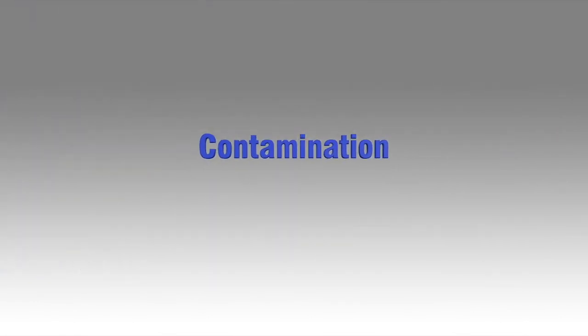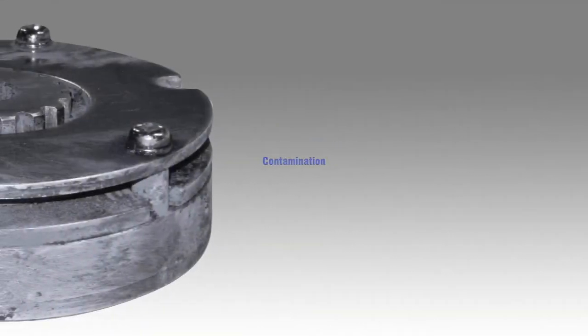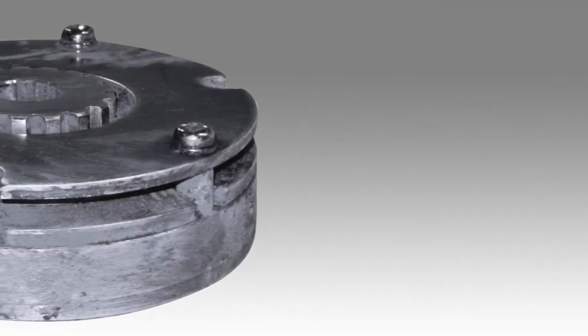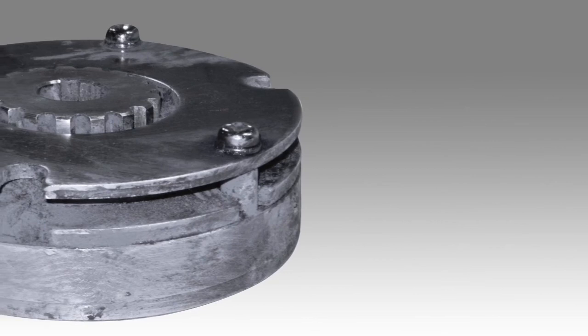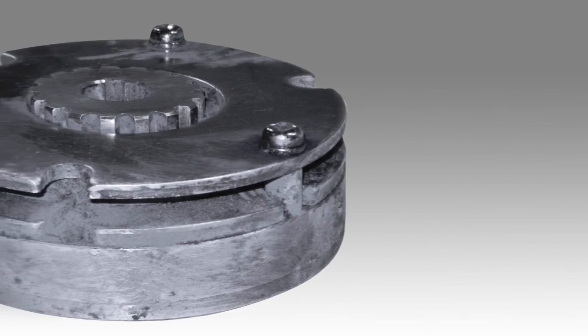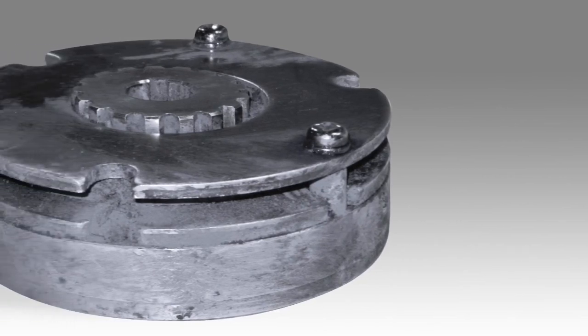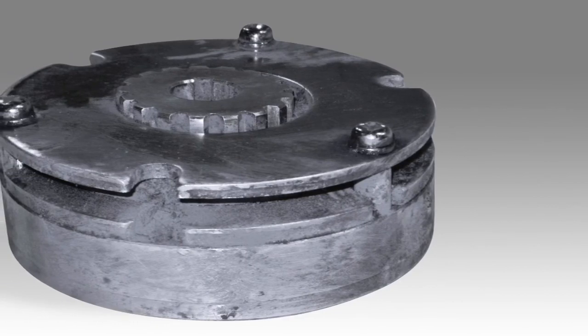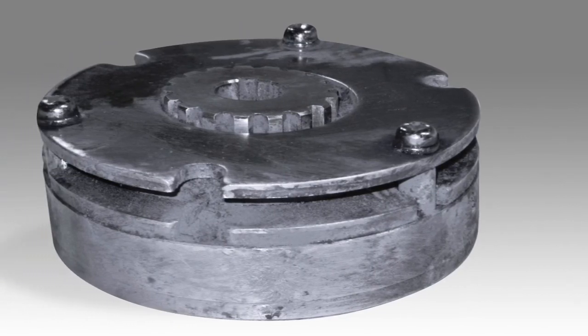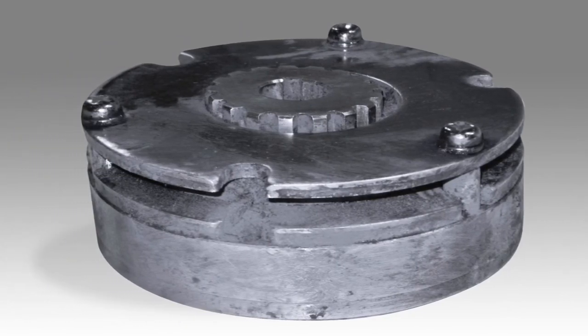Contamination. The brakes are to be used in dry environments only. Contaminants such as oil and grease should not be permitted to contact the friction surface at any time. If the friction material becomes contaminated, the brake will probably need to be replaced.